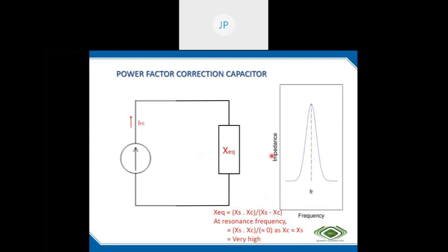This is the impedance versus frequency curve. As the term XL minus XC approaches 0, the impedance increases, and at 0 it is maximum, and again it deviates from 0. This is a bell-shaped curve. If we inject 300 amps into this equivalent impedance, the voltage developed follows the same wave shape, frequency versus voltage. That means the voltage is amplified too much at the resonance frequency.